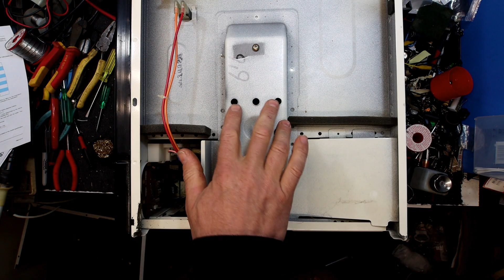So pretty standard stuff. We could check the capacitor, I guess, see if that's got any issues. As far as value goes, we're going to have to short it out, but this one you really have to either remove the fan or drop the thing down. It should still be earthed through the transformer, but don't take that for granted. So if we pull this out a bit, being careful not to touch anything, we'll just short the two sides to ground.